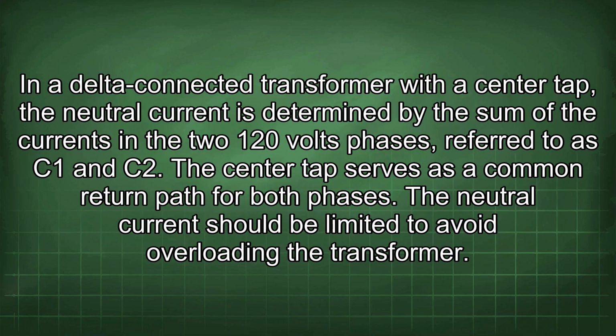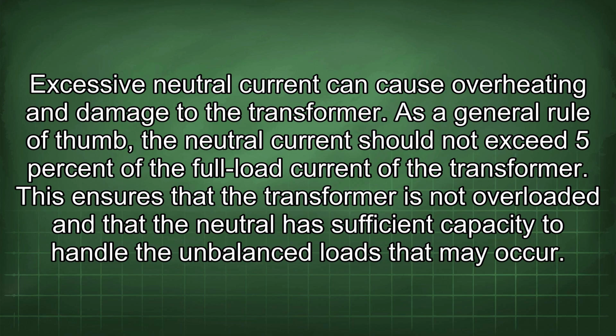In a delta-connected transformer with a center tap, the neutral current is determined by the sum of the currents in the two 120 volts phases, referred to as C1 and C2. The center tap serves as a common return path for both phases. The neutral current should be limited to avoid overloading the transformer. Excessive neutral current can cause overheating and damage to the transformer.